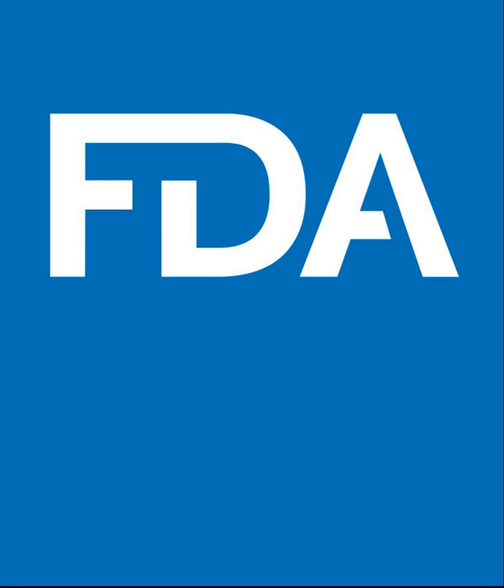Topic: Automatic Class 3 Designation (De Novo Classification). The Food and Drug Administration Modernization Act of 1997 created Section 513(f)(2) of the FD&C Act, which obligated the FDA to establish a risk-based regulatory system for medical devices. As a result, the FDA established a "de novo" pathway for devices that would automatically be classified as Class 3 because there was no already existing device that could be used as a predicate for a 510(k) submission, but for which general controls or general and special controls could provide a reasonable assurance of safety and effectiveness.